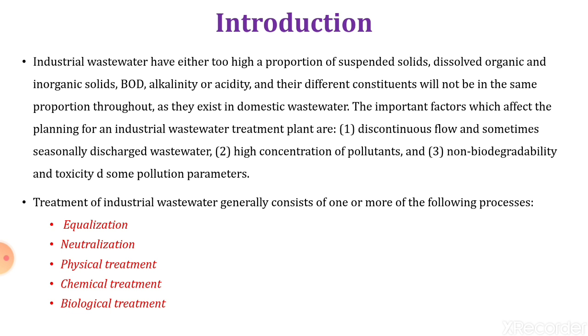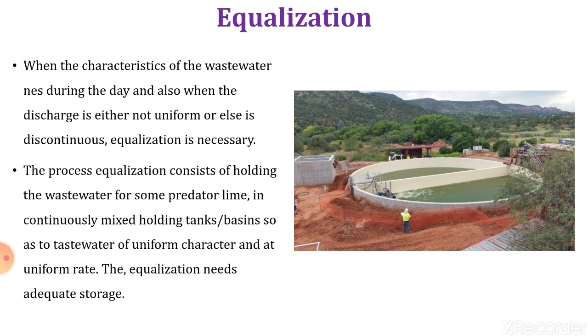Treatment of industrial wastewater generally consists of one or more of the following processes: equalization, neutralization, physical treatment, chemical treatment, and biological treatment. Let us see each treatment in detail. Equalization is necessary when the characteristics of wastewater change during the day or when the discharge is either not uniform or continuous. Equalization consists of holding wastewater for some predetermined time in a continuously mixed holding tank or basin so as to produce wastewater of uniform character and at a uniform rate.